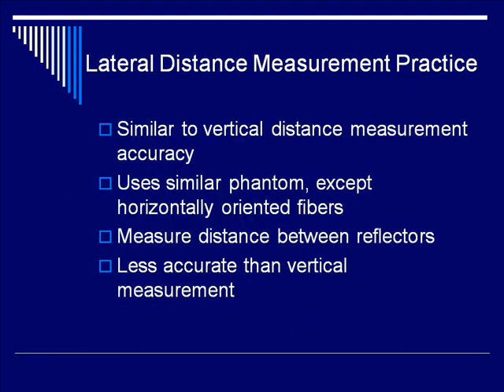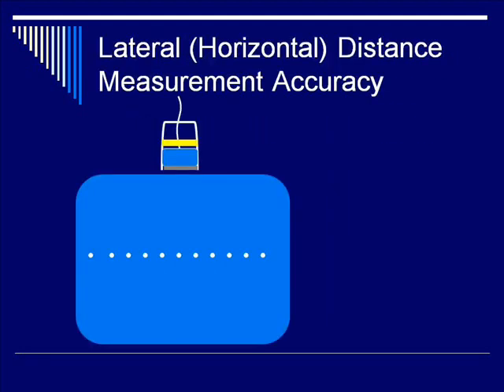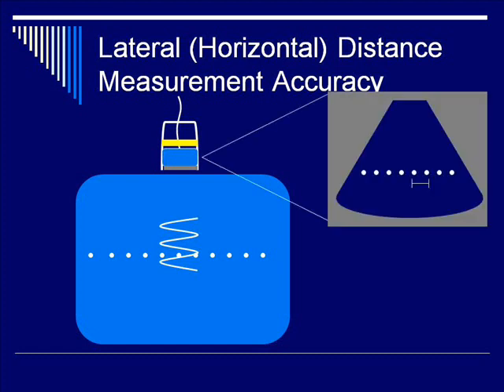The next thing to discuss is horizontal distance measurement accuracy, also called lateral distance measurement accuracy. It's very similar to vertical distance measurement accuracy. You use a phantom with horizontally oriented fibers instead of vertically oriented fibers, and using calipers you measure the distance between reflectors. Remember that this number will be less accurate than vertical measurement because our highest accuracy and highest resolution is in the axial direction.